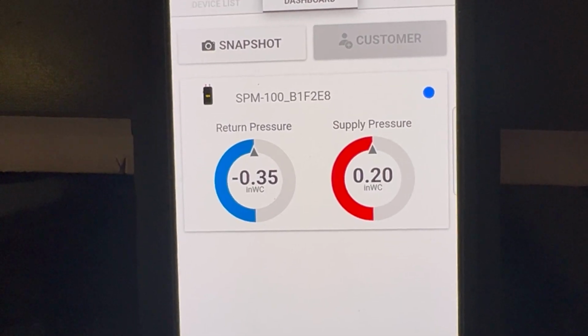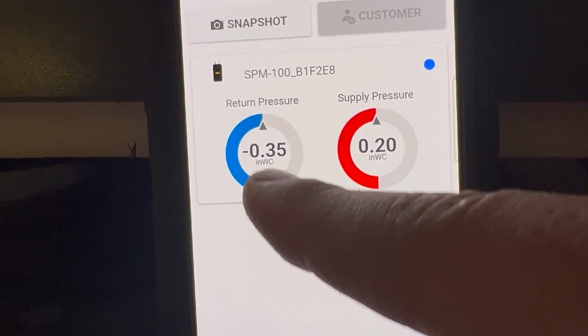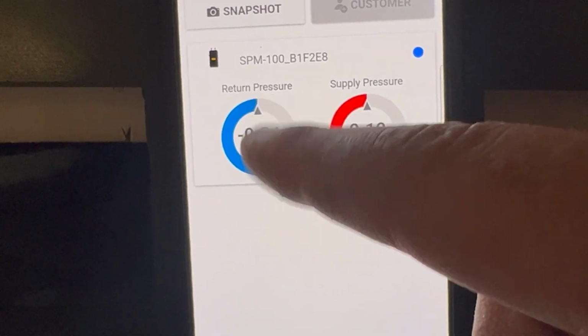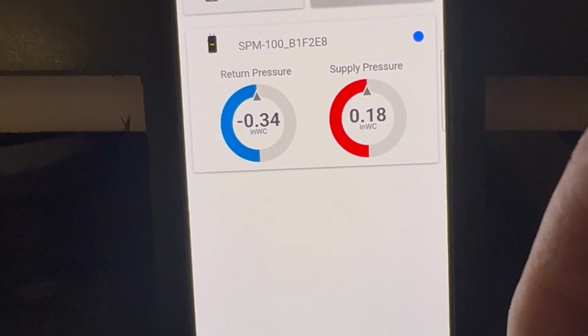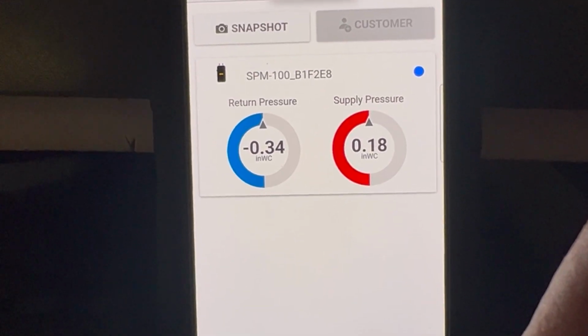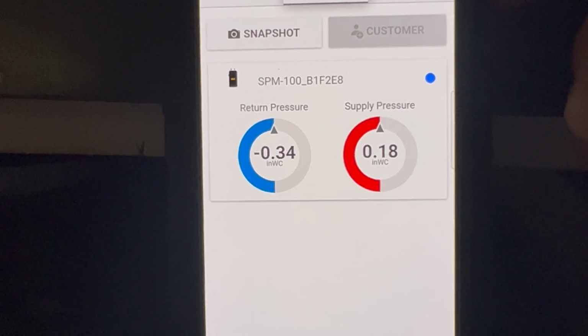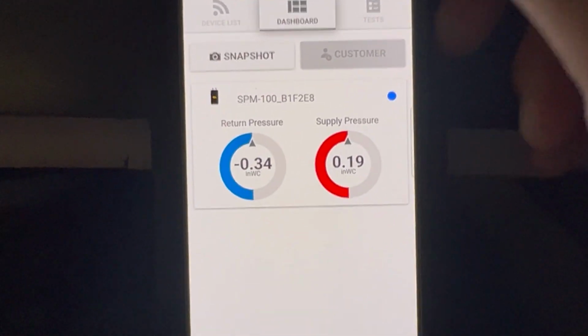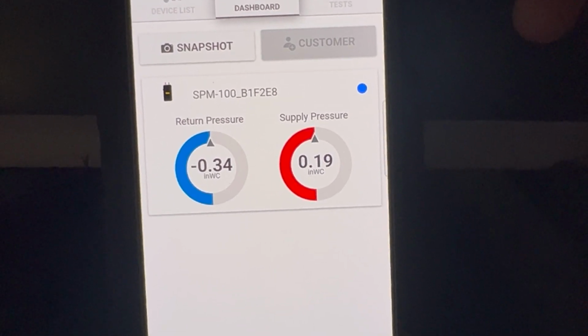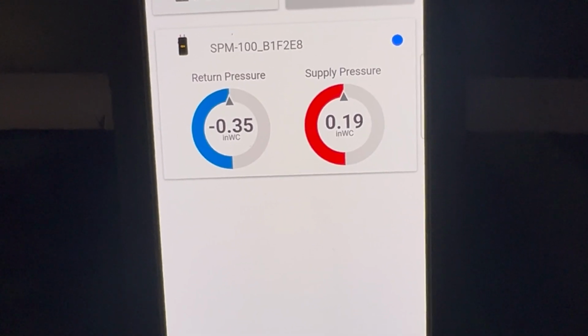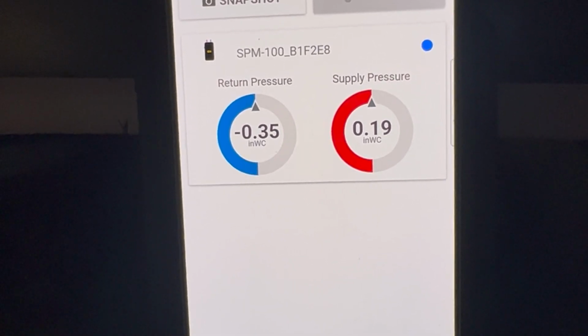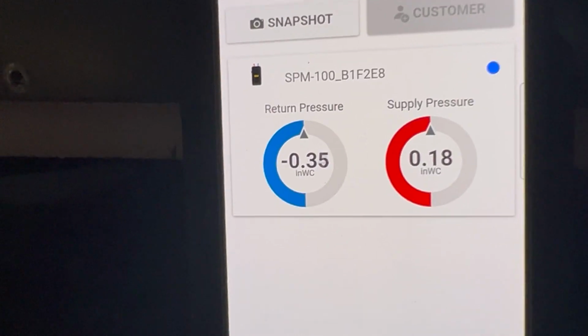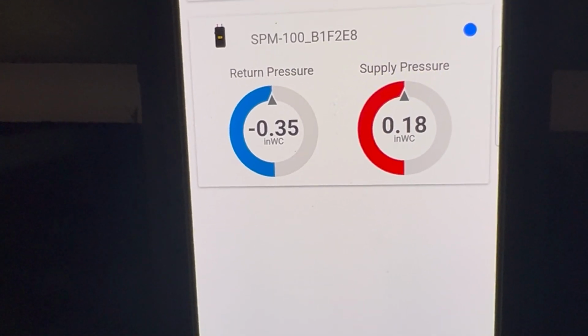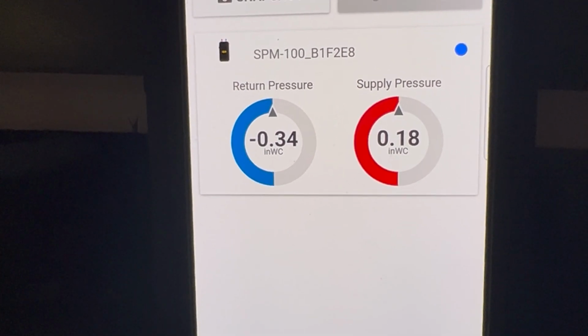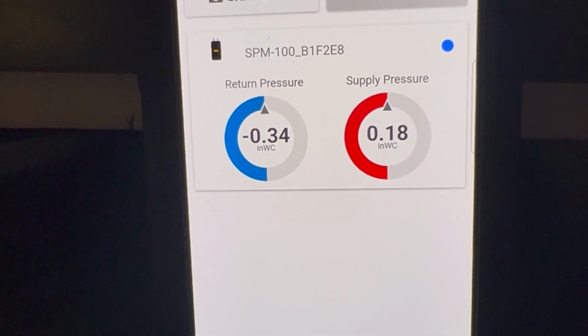So now we're gonna check the static pressures, make sure everything's fine. This is how much we got. Don't mind the color. If you see, it says return pressure 0.35 and supply 0.18. We're right on point. We always try to be 0.50 and below static pressure, 0.5 and below. So we're right on point. I mean, you can go up a little bit or down, but it should be fine. At least we know there's no big restriction in the ductwork that could have caused this blower motor to go bad.